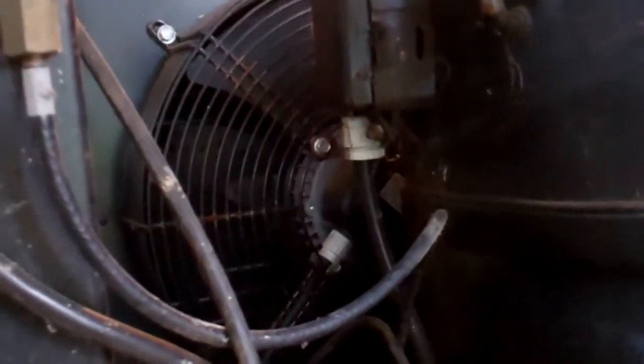I fitted it and it didn't work. So I've been playing around with it, trying to work out what was the start winding, what was the run, because none of it was labelled up — no diagram with it. And there's a couple of problems. It's got these push-in terminals — not proper screw terminals on this side. And because the wires on the new motor were fatter than the old one, and the wire I used on the capacitor was fatter, when I pushed them in I think it stopped the other ones connecting, which is why the motor didn't run — because then when I tried it the original one stopped working as well.